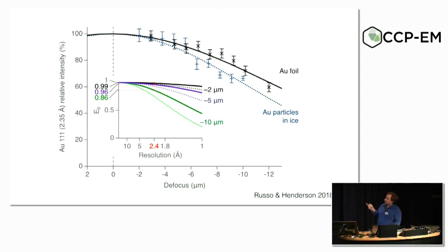And so you can also extrapolate this as a function of energy and see how much this is going to affect you as you go to lower energy, because going to lower energy is a problem for specimens that charge. Delta E over E is roughly how these things scale, right? So bigger charge, lower energy beam for the same charge, you're going to have a worse problem.